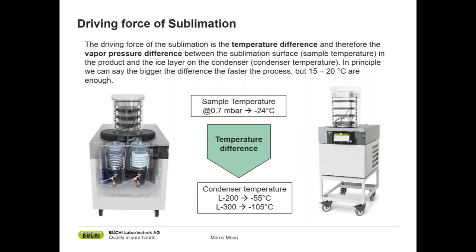The vapor formed moves down to the condenser where it is collected. We need a temperature difference between the sample and the condenser temperature; this creates a suction and the vapor moves downward to be condensed again. In the L200, we have a condenser temperature of minus 55 degrees. In the L300, we have a condenser temperature of minus 105 degrees. What we need for proper freeze drying is a difference between those two temperatures of 15 to 20 degrees.